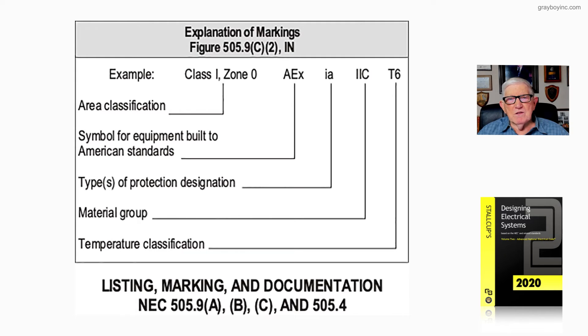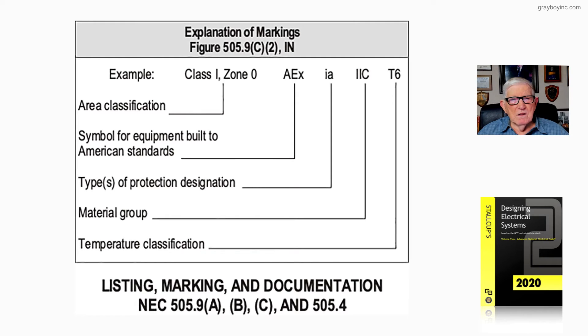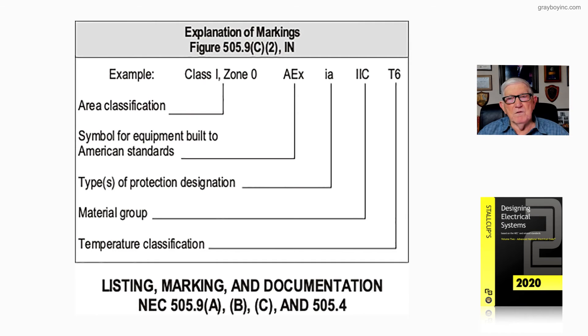Then the type of protection designation is IA. Remember we looked at all those types of equipment in 505 — I believe it's 505.9b. And notice the material group is 2C. We looked at the groups and compared IIA, IIB, IIC to our groups A, B, C, and D in the divisions.